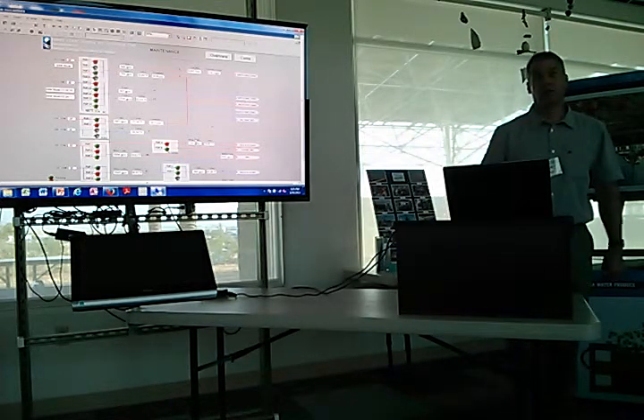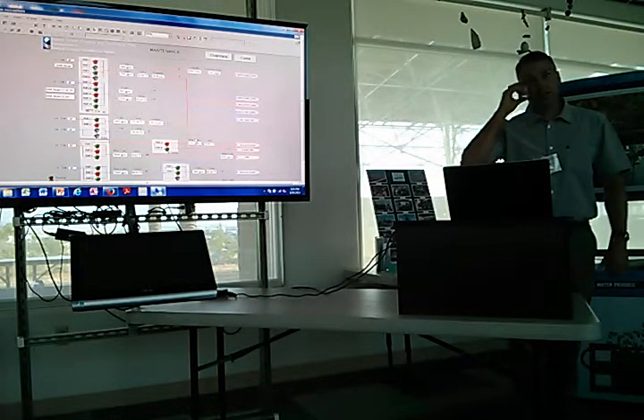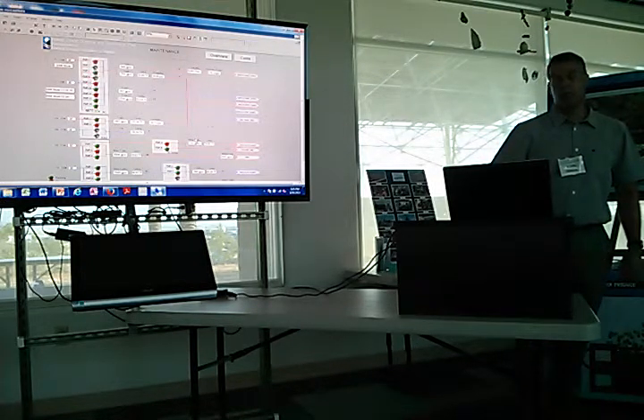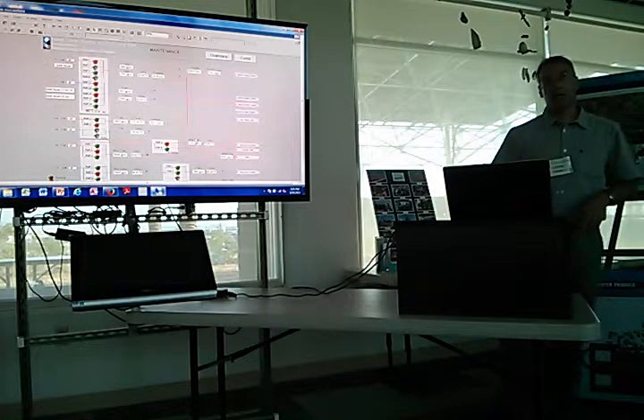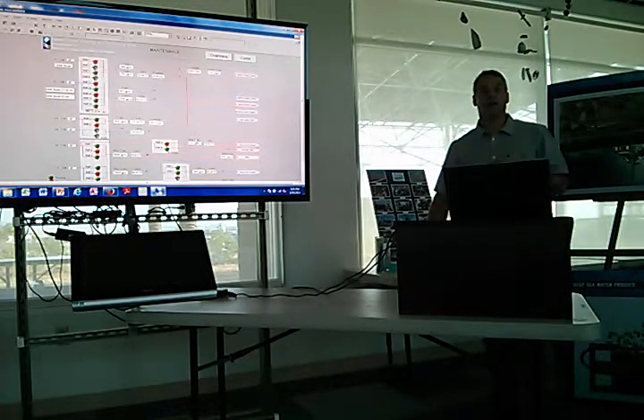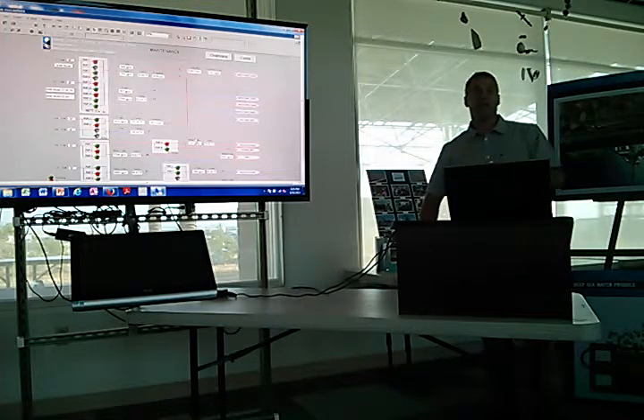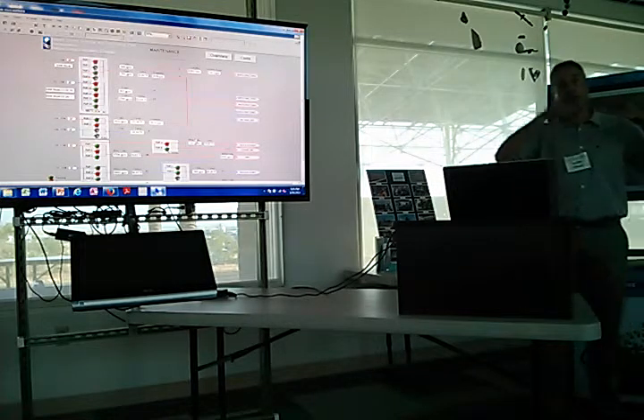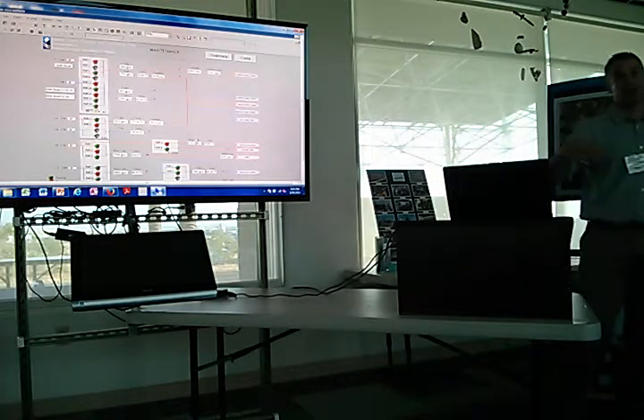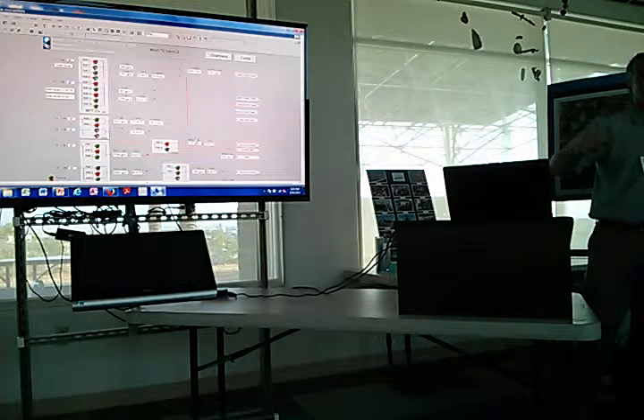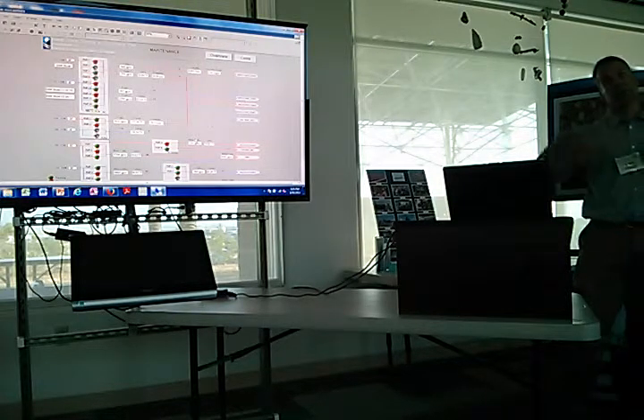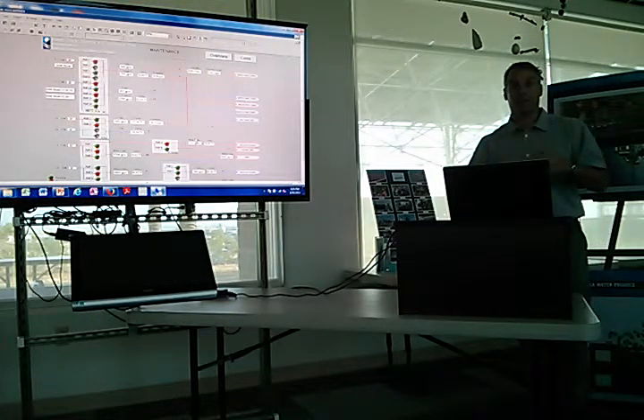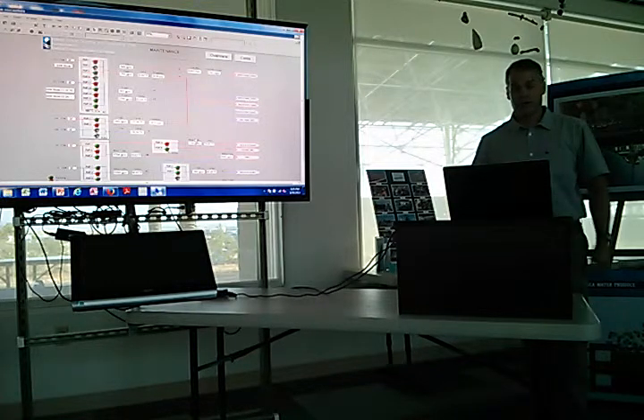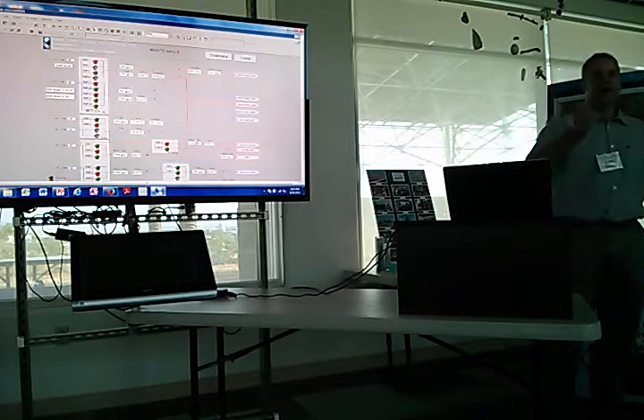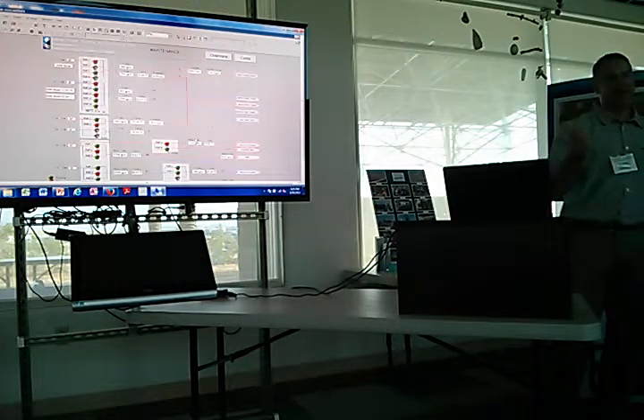Those pumps out by the lighthouse? Yes, those are the controlling pumps, and we have others on steady state. That's what they mean by variable frequency drive - the set point is the pressure. So when someone opens a valve, the pressure drops in the pipe and the pump spools up and maintains that pressure, so our clients will never have a valve open up without water coming out.